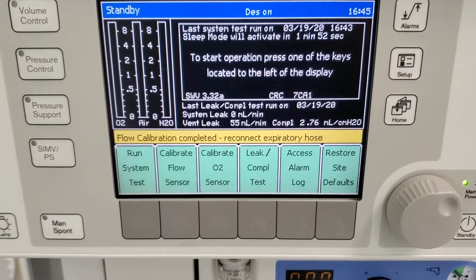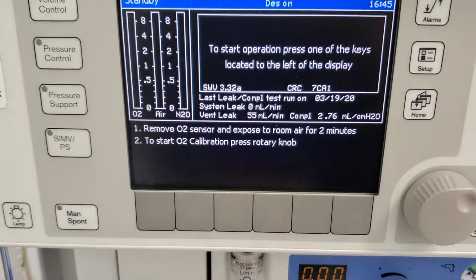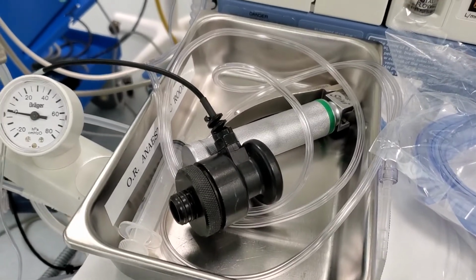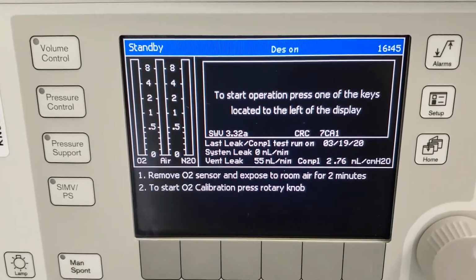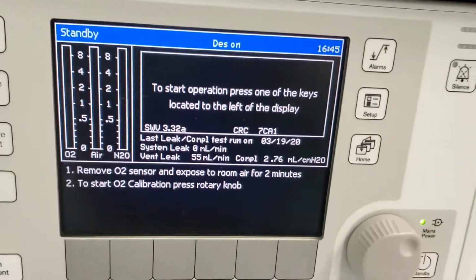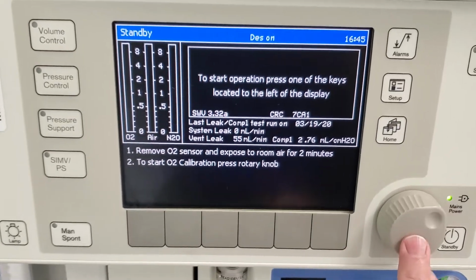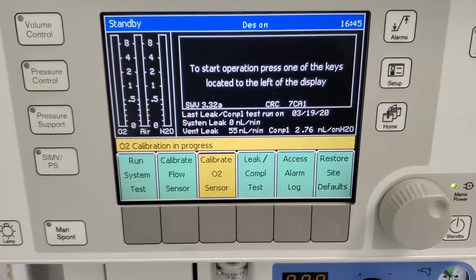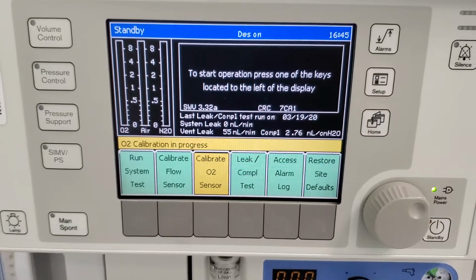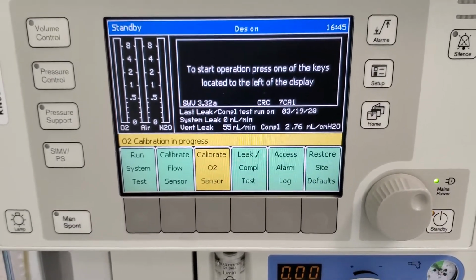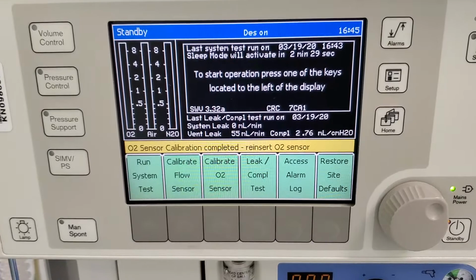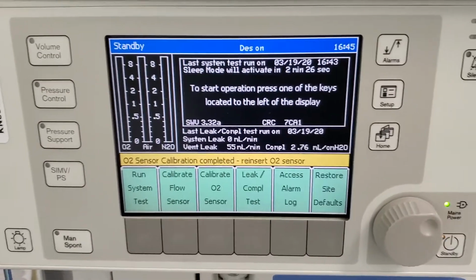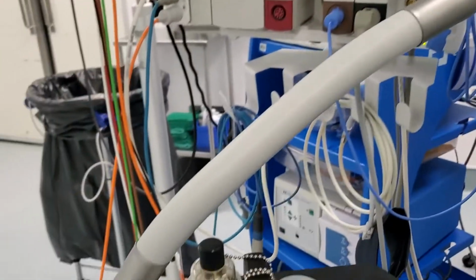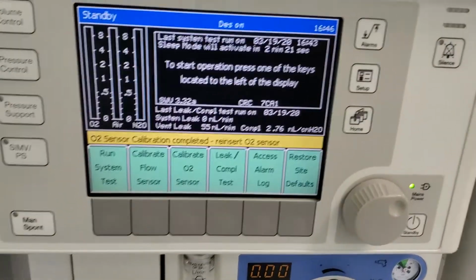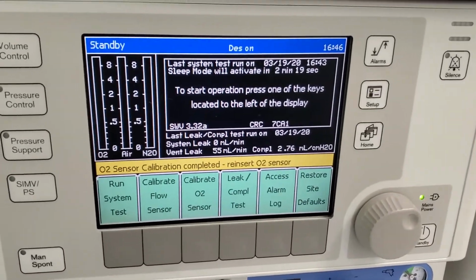The second sensor to calibrate is the O2 sensor. That is what I showed you at the beginning of the video. So basically it prompts you again, remove the O2 sensor. So just basically removing it from its housing there. We want it exposed to room air for 2 minutes and press the knob to start the calibration. So both that test and the flow sensor test are quite quick. They don't really take a lot of time. All right, so that has been completed. If we were to use the machine, we would reinsert it into the inspiratory port at this time. I'm gonna leave it out because we're not actually using it on a patient.